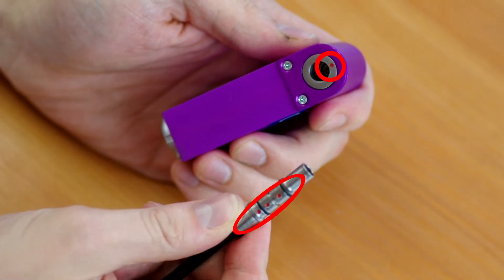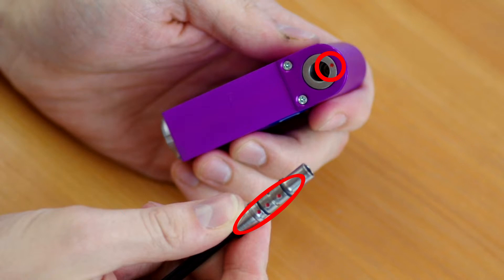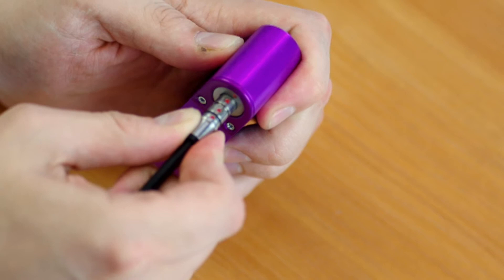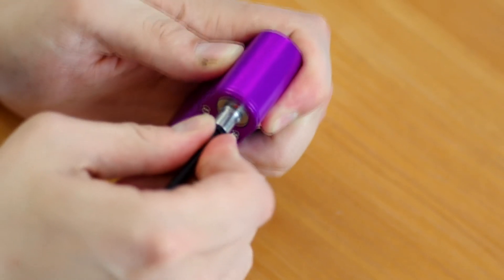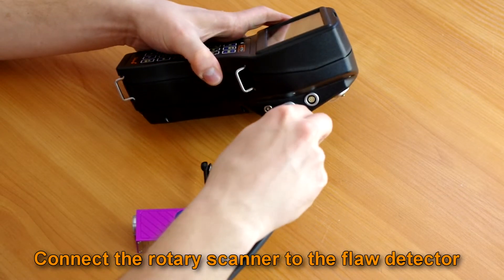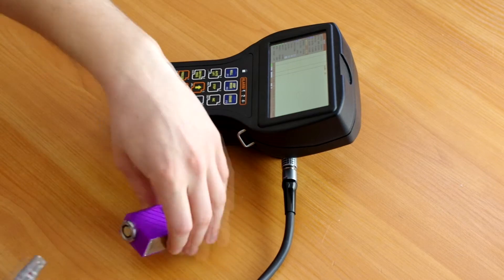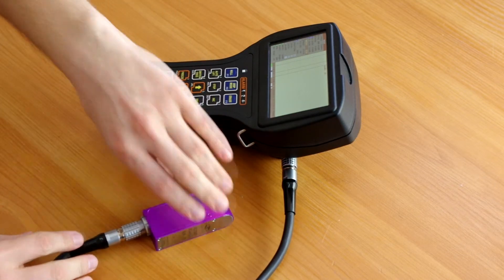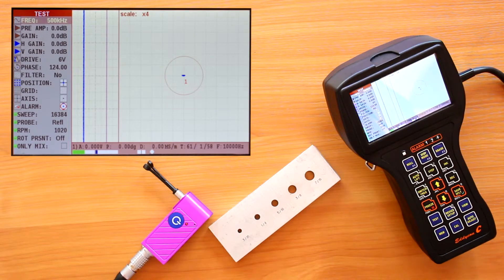Rotation probe. Connect the ECP to the rotary scanner. Markings on the housing of the probe and scanner should coincide. Insert the ECP into the scanner without applying excessive force. Connect the rotary scanner to the flaw detector using a connecting cable.